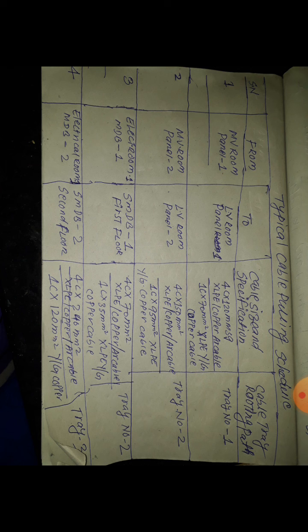Less than half of 120, which is 60, is not usable, because we require at least half the value of the power cable. Okay, and the next one is 70, which is available in 70 mm square, so we can use 70 mm square. And serial number 2, the next cable is MV Room Panel-2.